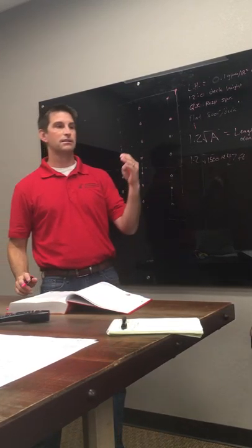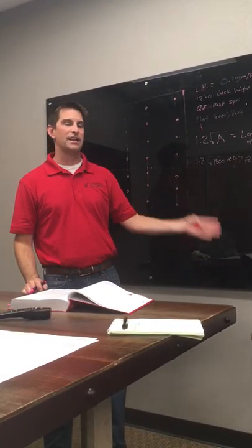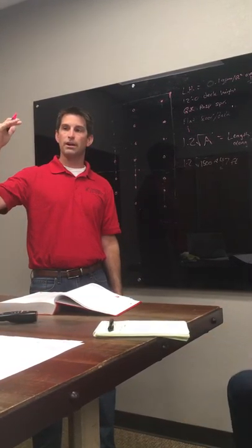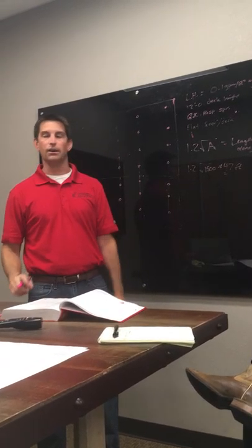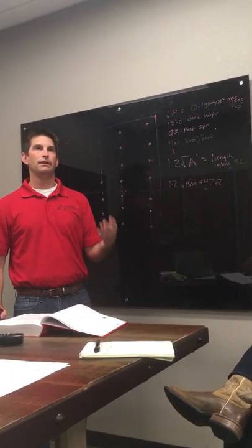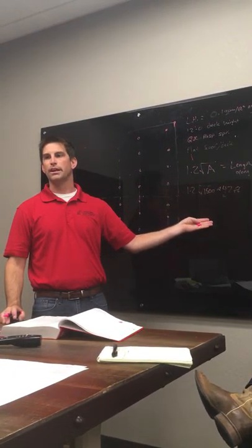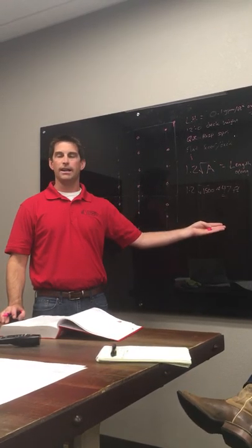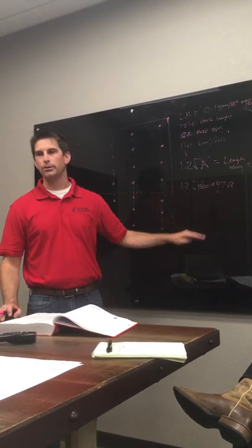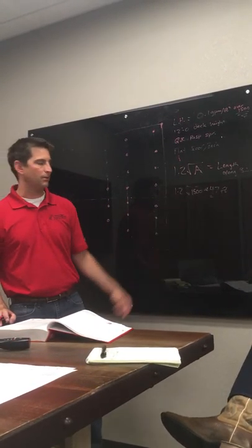So basically it says 10-foot ceiling, that's the best case you can ever have. Even if it's an 8-foot ceiling, you can't go less than 10, right? If you have an over 20 foot ceiling, you can't do this reduction in your area. So it needs to be between 10 and 20? It needs to be anywhere under 20. It's just that if it's under, there's an equation that gives you a percent of reduction. If you plug in 8 foot, you're going to get a higher percent of reduction. They cap you at 40%, and that's a 10 foot ceiling. Okay. So you'll see it when we start working it out.